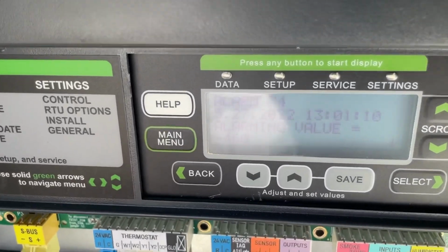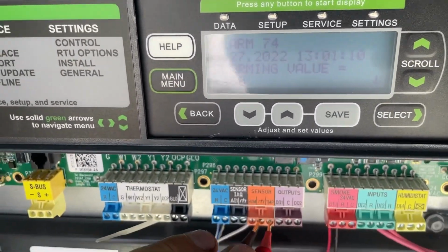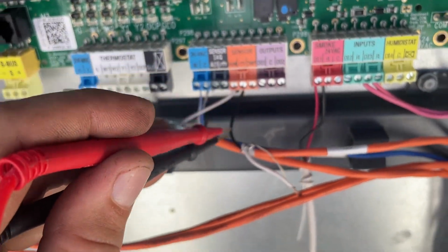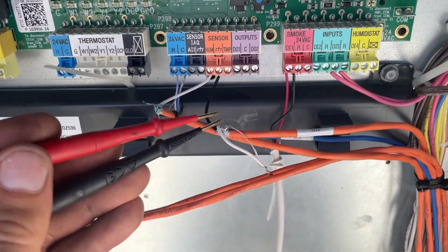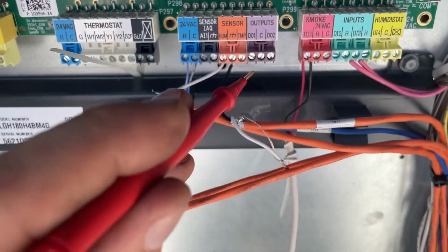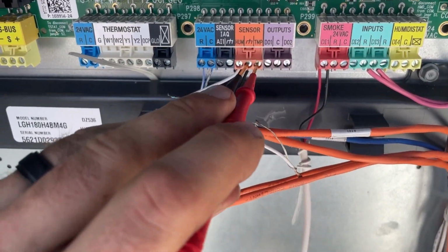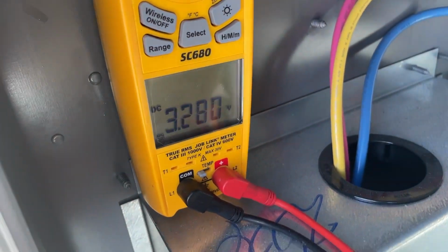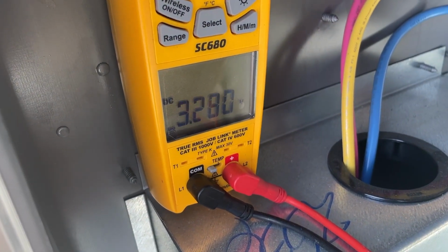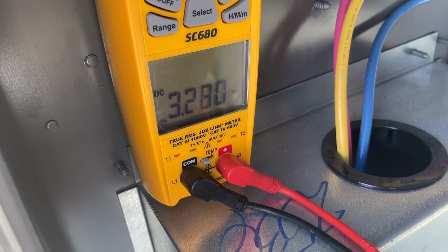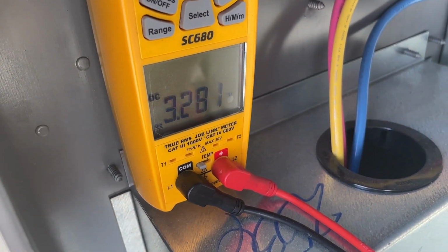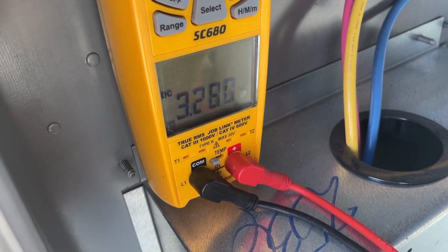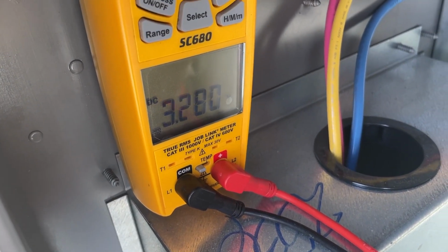All right, so I've opened the zone air temp and of course created an alarm. Now, because I'm taking that resistor out of circuit, there is no voltage drop. We have an open circuit. So let's look at what we're reading. That is 3.3. And the reason I knew that is based on what it was before, the fact that it's kind of like halfway in its range, and this is a very common logic voltage. Another common one is 5 volts.